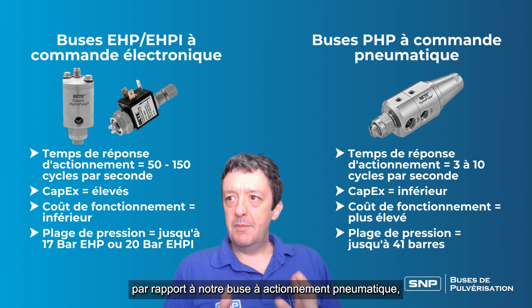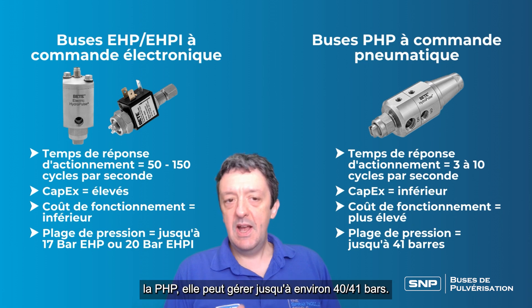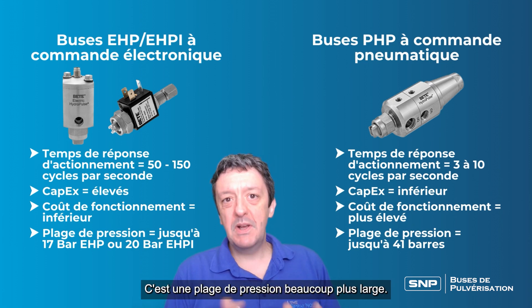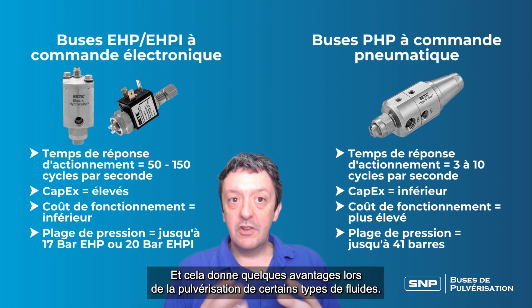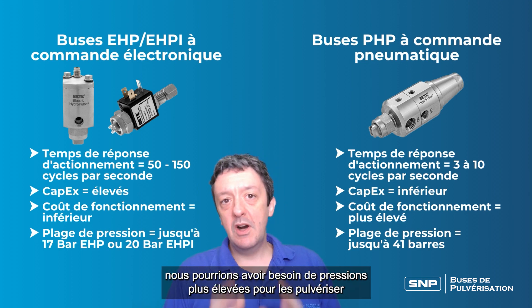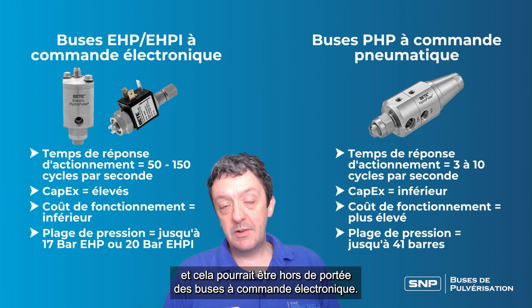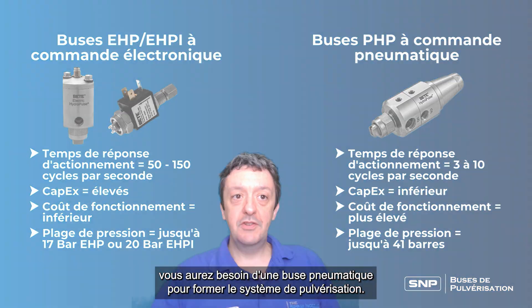Now let's compare that to our pneumatically air actuated nozzle, the PHP. This can handle up to about 40 to 41 bar — a much bigger pressure range. That gives some advantages when spraying certain types of fluids. If we're looking at spraying highly viscous fluids, for example, we might need higher pressures, and that might be out of the range of the electronically controlled nozzles, in which case you're going to need something like an air actuated nozzle.